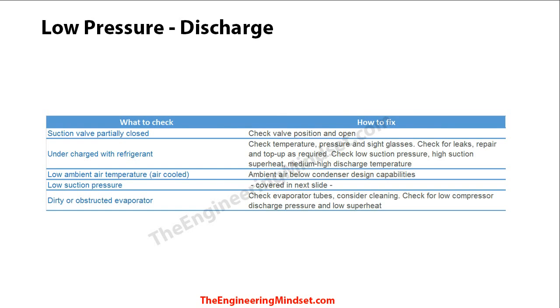Moving on to low pressure discharge: the suction valve might be partially closed — uncommon but worth checking. On the flip side of overcharged refrigerant, if the system is undercharged you'll have low discharge pressure. Check that the refrigerant charge is sufficient, and if you suspect it's low, top it up.